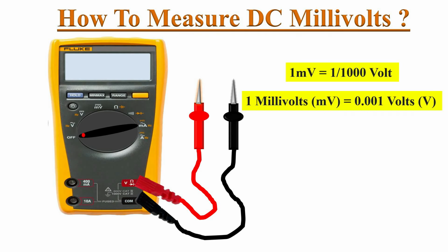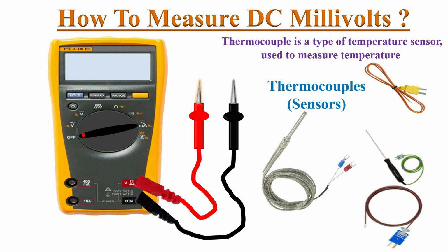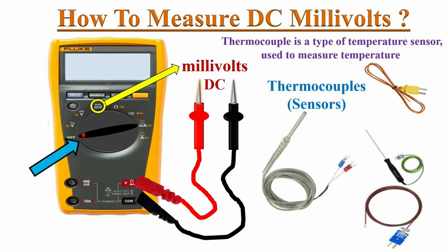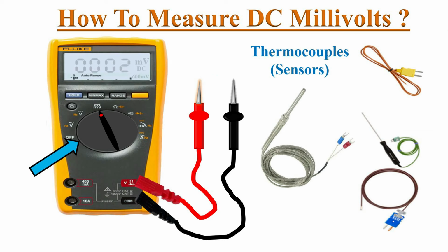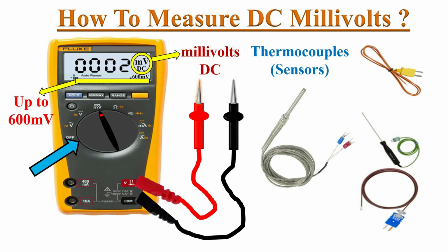Now next topic, how to measure DC millivolts with a digital multimeter. Millivolts are very small voltages. 1 millivolt equals one thousandth of a volt. Sensors like thermocouples produce small voltages in terms of DC millivolts in an electric circuit. To measure millivolts, identify the DC millivolt symbol on the dial and turn the knob to that position. The meter turns on and the DC millivolt symbol appears on the screen. We can measure up to 600 millivolts with this DMM.